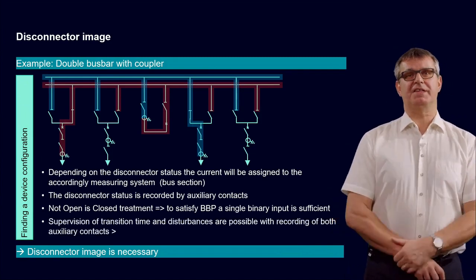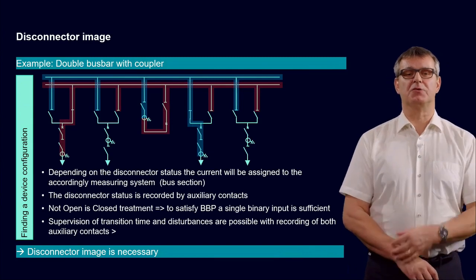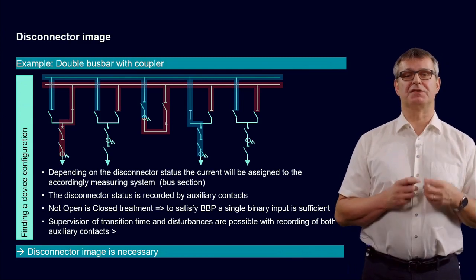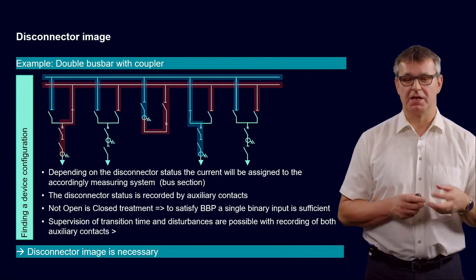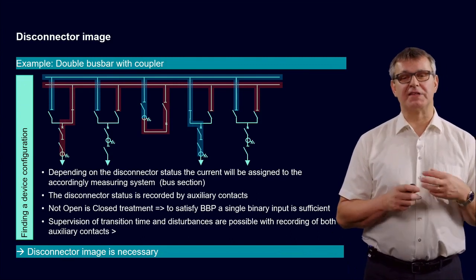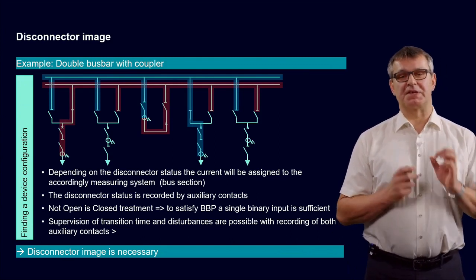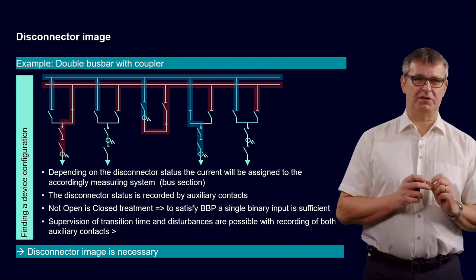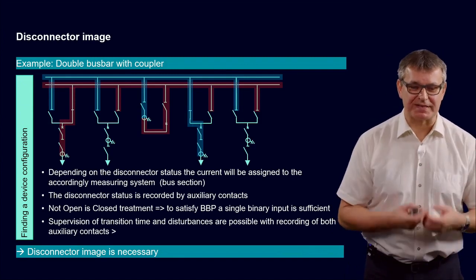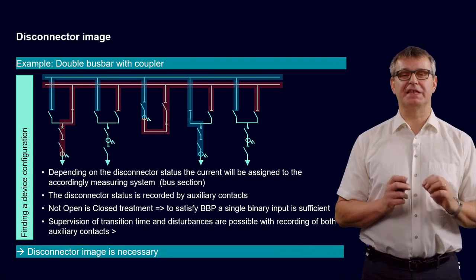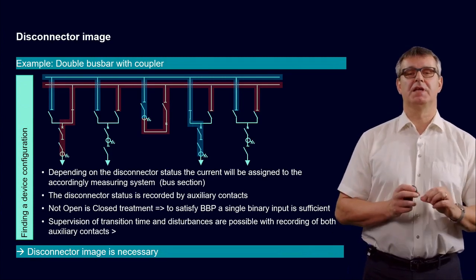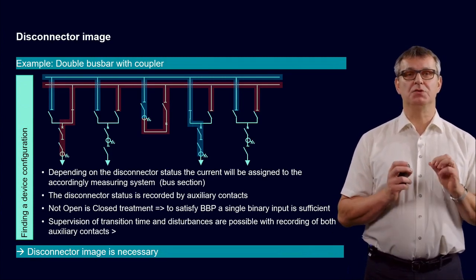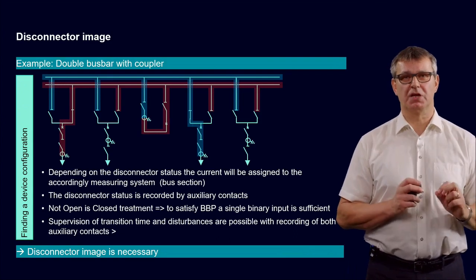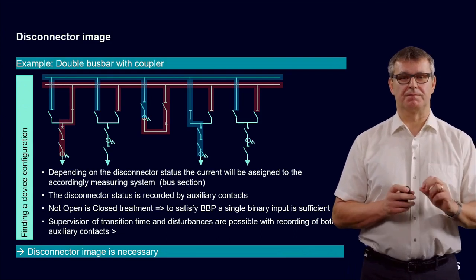Of course, only if we have two binary inputs can we really supervise the transition time, and also detect a runtime error or anything else. But for our example here, just to make an exercise and to show that it's possible in principle, we will use only one binary input for the disconnector position.